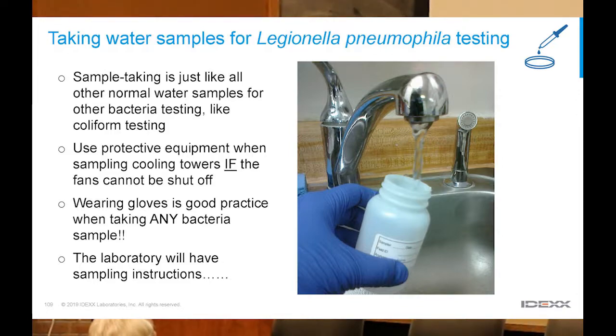When you would need protective equipment is if you're going in and it's an outbreak investigation, and you know that there are probably high concentrations, and you're going in a cooling tower, taking samples from the bottom, and the fan's blowing. Turn the fan off. You can probably wear a mask. You definitely wear gloves, and then you can take your samples. The good thing about using an accredited laboratory is they will give you instructions on how to take the sample.